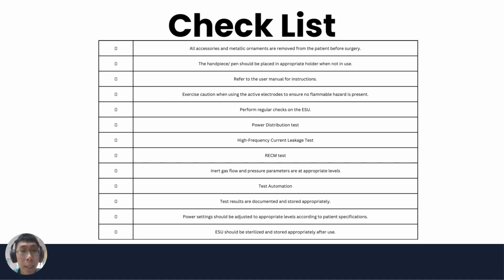Checklist. All accessories and metallic ornaments are removed from the patient before surgery. The handpiece should be placed in the appropriate holder when not in use. We should always refer to the user manual for instructions. Exercise caution when using active electrodes to ensure no flammable hazard is present. Perform rigorous checks on the ESU. Perform power distribution tests, high frequency current leakage tests, REM tests. Inert gas flow and pressure parameters are at appropriate levels. Test automation: test results are documented and stored appropriately. Power settings should be adjusted to appropriate levels according to patient specifications. ESU should be sterilized and stored appropriately after use.